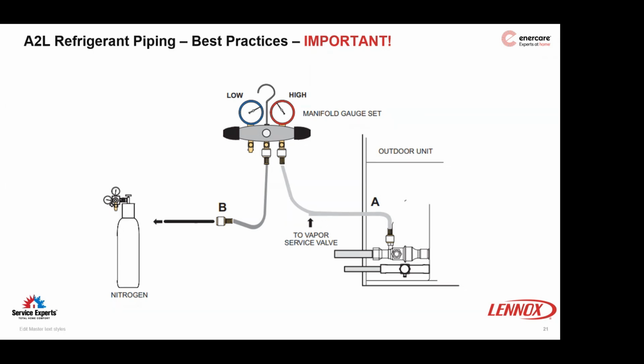Notice how this diagram uses the high side gauge and the hose connected to the low side service valve. Often our test pressures exceed the design safe working pressures for the low side gauge, and following this method can prevent any possible damage to that more sensitive low side compound gauge.